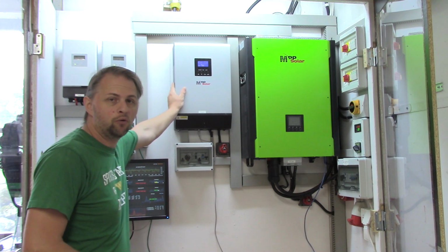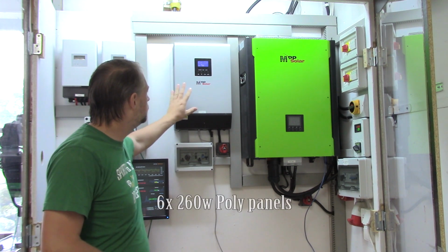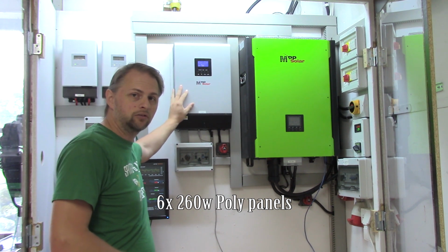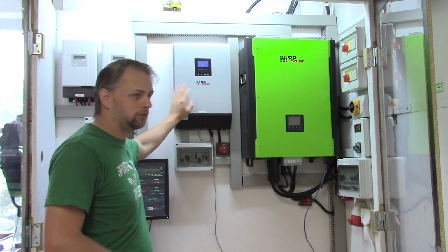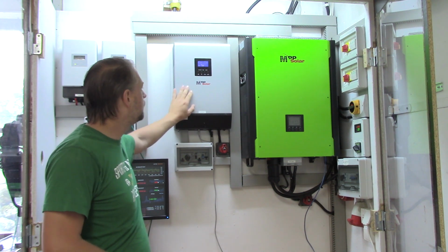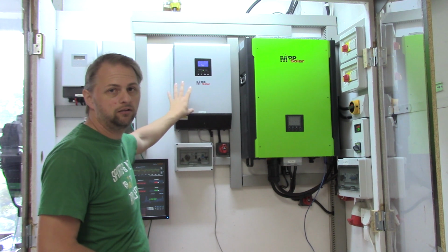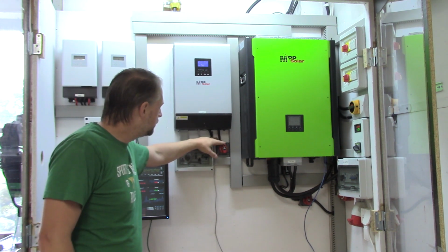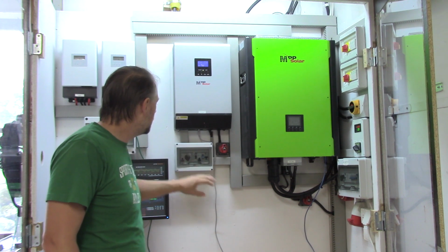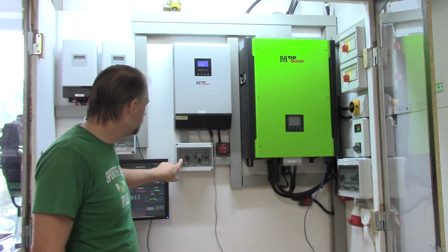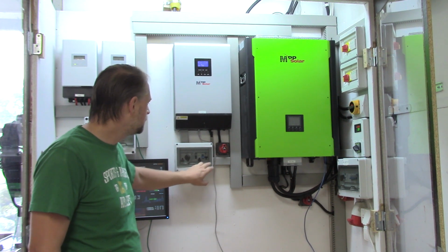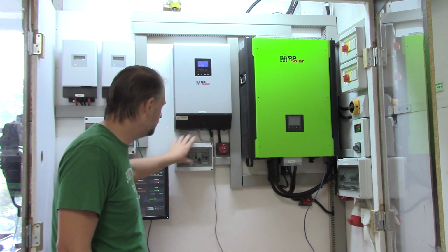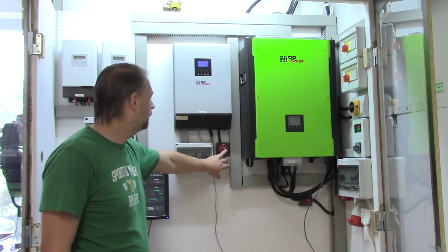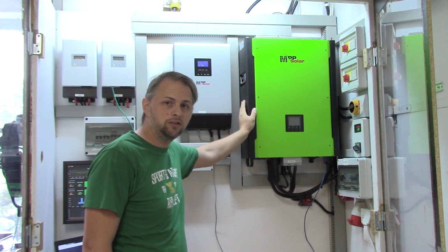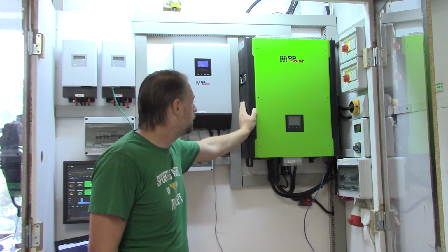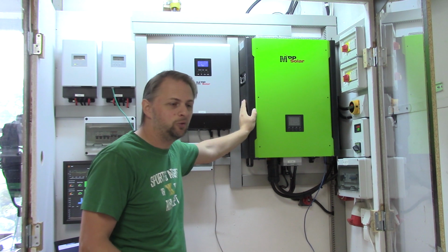We have the PIP4048 here. This one is just running six 250 watt panels currently, and the reason for that is because it's just a test station kind of, and I will have it for running high current one phase loads. This one is tied to the battery with this breaker here, and it has this breaker box for incoming grid, outgoing AC and incoming PV, so everything is tied in the same box except the battery itself. This is a 10 kilowatt 3-phase unit from MPP Solar, and it has been working very good for me, except it has some tweaks and quirks.